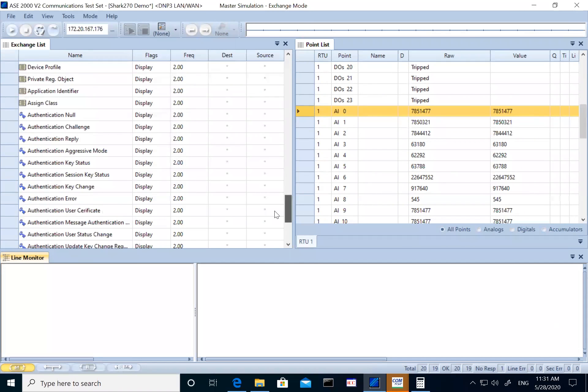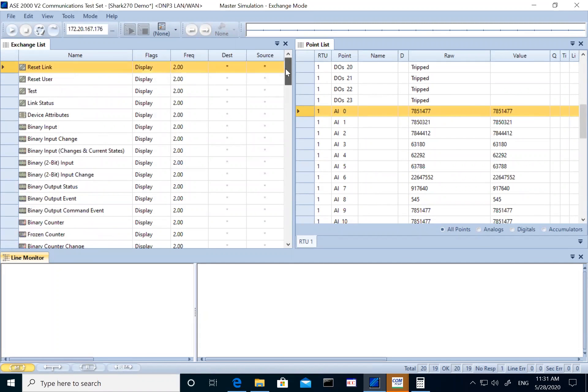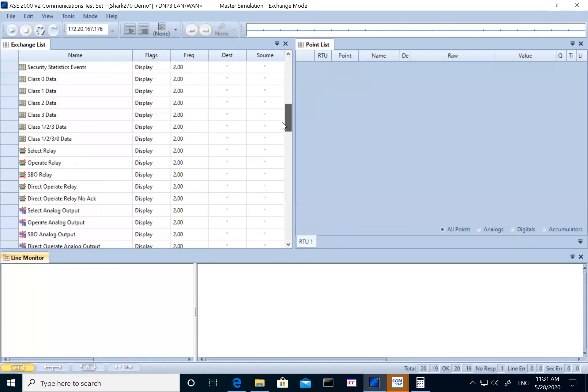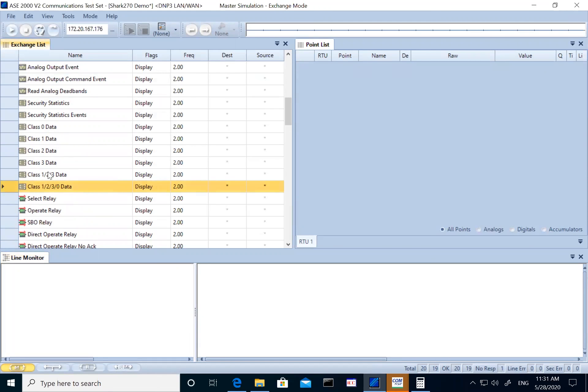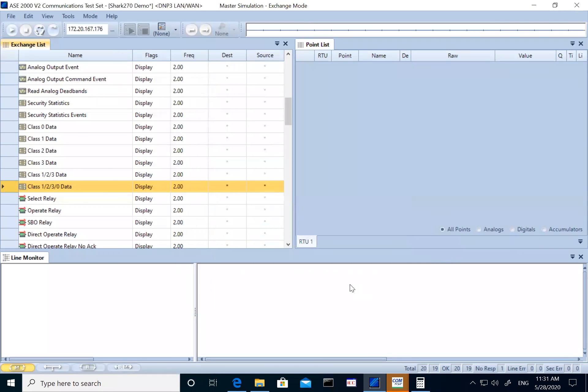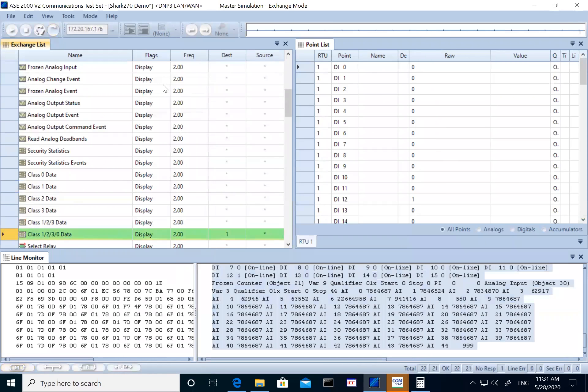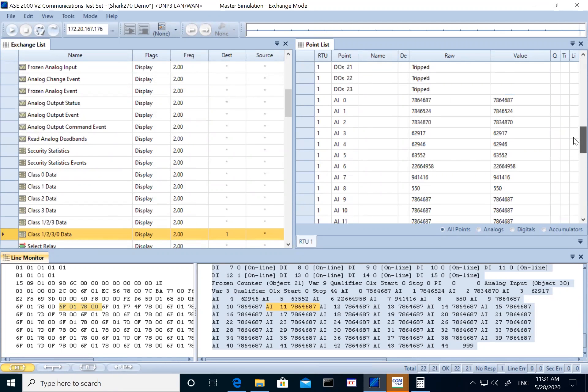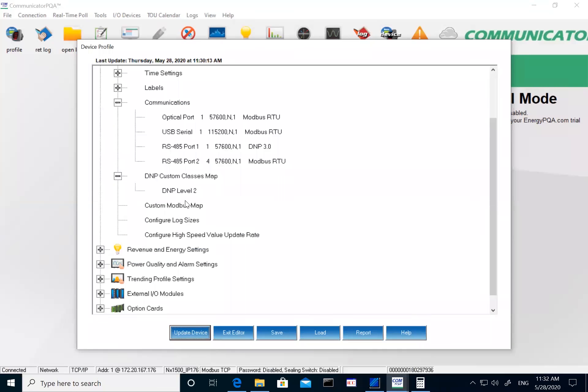On the left it shows me options for requests — I can pull any of these objects or sections to get meter readings. For example, to pull everything set up on the meter, I have the option for class 0, 1, 2, 3. I double-click on it, put in the destination address — I have set up 1 as my meter address — select it, and hit Send. The meter responds; this is the raw DNP message, and on the right it shows me the points and values.